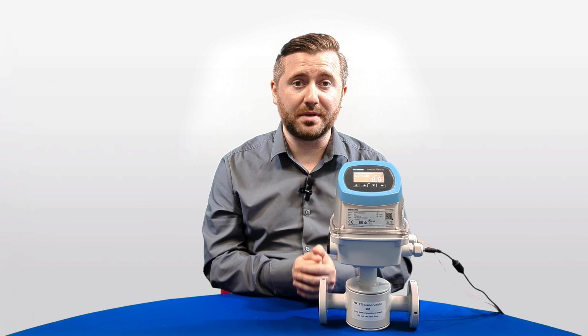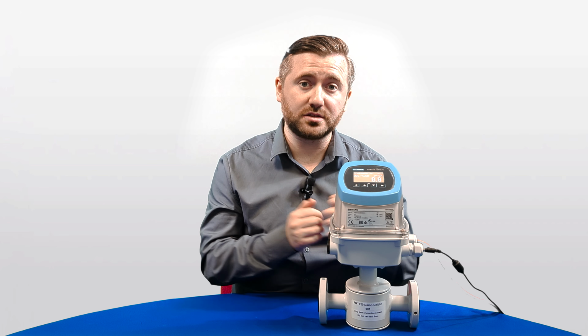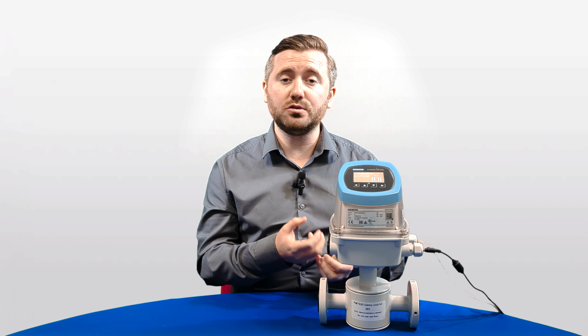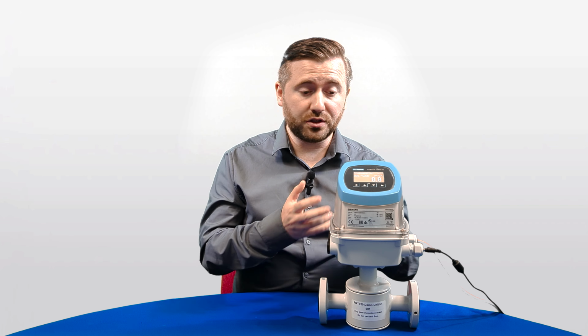One key notable feature is that the analog output with the 4 to 20 milliamp range, previously used to monitor flow rate within the meter, can now be used to measure the conductivity of the fluid. This will be a massive help for examples like data centers or any circuit with glycol content for heating or cooling. By measuring the conductivity of the fluid automatically, you can measure what your glycol levels are like. This prevents the need for other peripheral devices for more constant logging - the meter takes care of that for you. As the conductivity changes, you know that perhaps your glycol levels are too high or too low, and you can take immediate action.